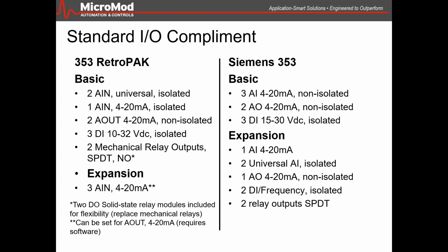Those three analog inputs can deliver transmitter power supply. They can just be passive 4 to 20s, receiving a 4 to 20 signal rather than powering the 4 to 20 signal. They can also be a current output.